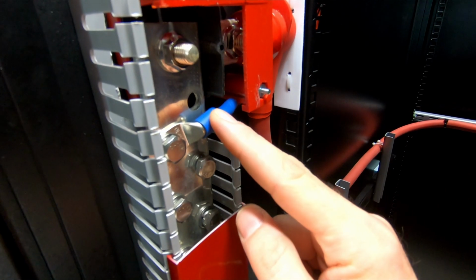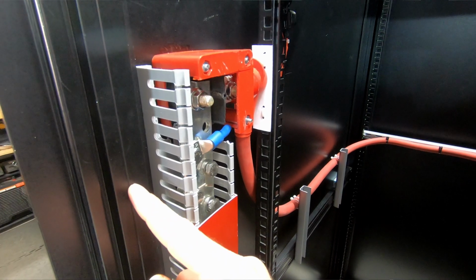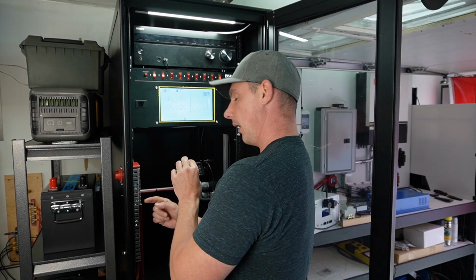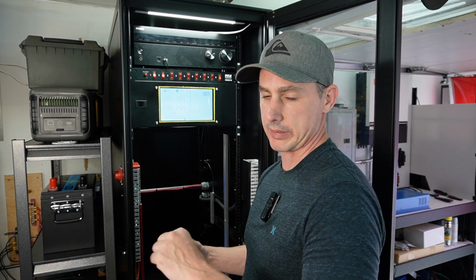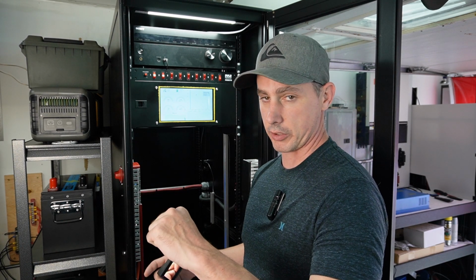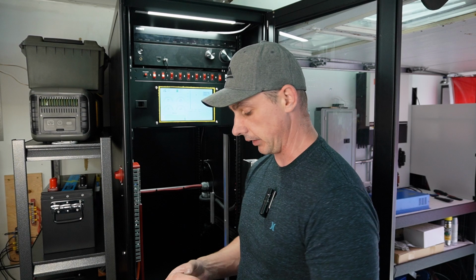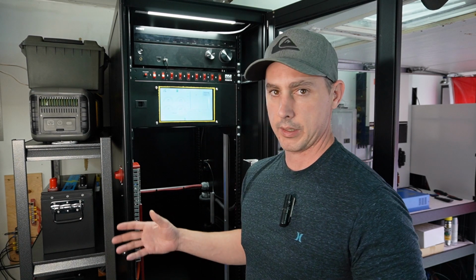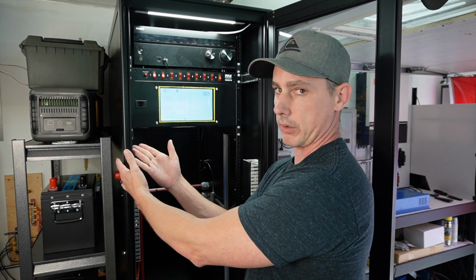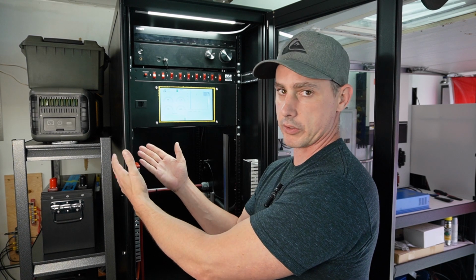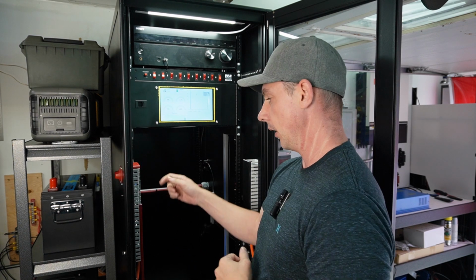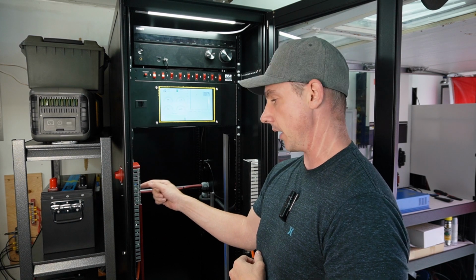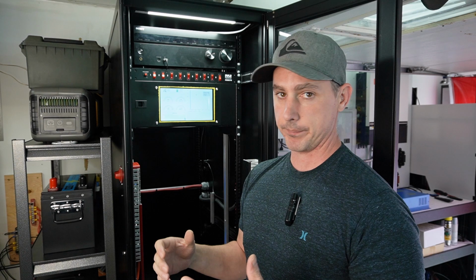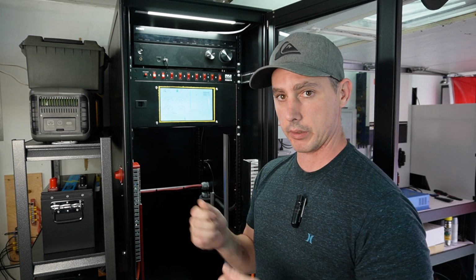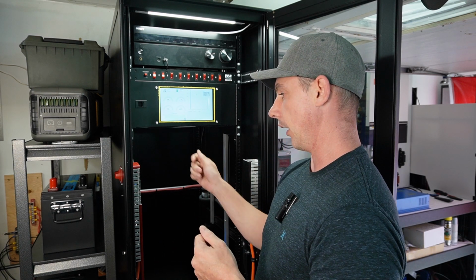Regardless, I was installing this temperature sensor and I was leaning up against the server rack case and my arm actually started to tingle and I felt I was getting shocked. So initially I kind of freaked out and I was questioning like, how is the metal case of the cabinet being electrified and my arm holding onto the socket, tightening up this bolt and then leaning against the case, how is that shocking me?